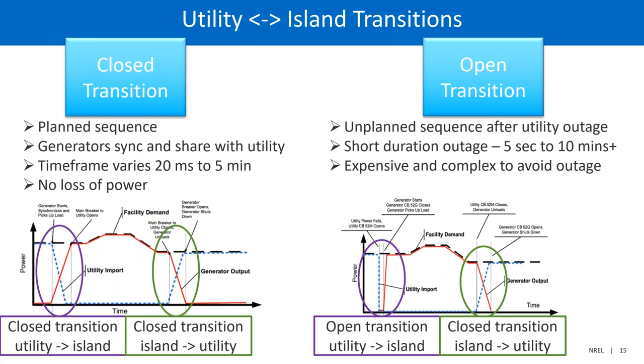This is typically a planned sequence, so you know it's going to happen. Ideally, your sources spin up, they start reducing what you're pulling from the utility, so they start producing power locally. When it gets to zero that you're pulling from the utility, you open up your device and now you're islanded. It's very smooth, there's no loss of power, and the time frame can be fairly quick.